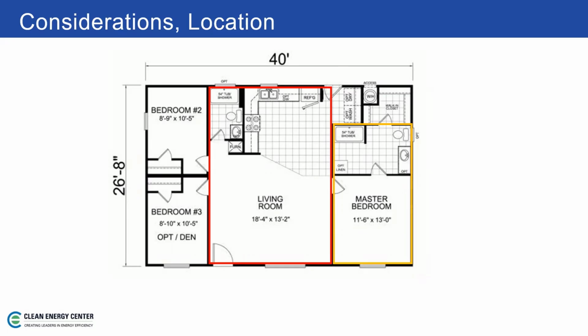Maybe when you do the 20 BTUs per square foot calculation, you come right out to a 9,000 BTU unit. If you have a 10,000 BTU unit available, or 12, whatever, you might want to bump it up 2,000 BTUs to help cover that. I would personally rather have an air conditioner that's slightly undersized than one that's oversized, because the key to a comfortable living environment, and to making these people feel comfortable with air conditioning, is to get rid of the humidity. The more humidity you can get rid of, the more heat, temperature-wise, that you can stand.